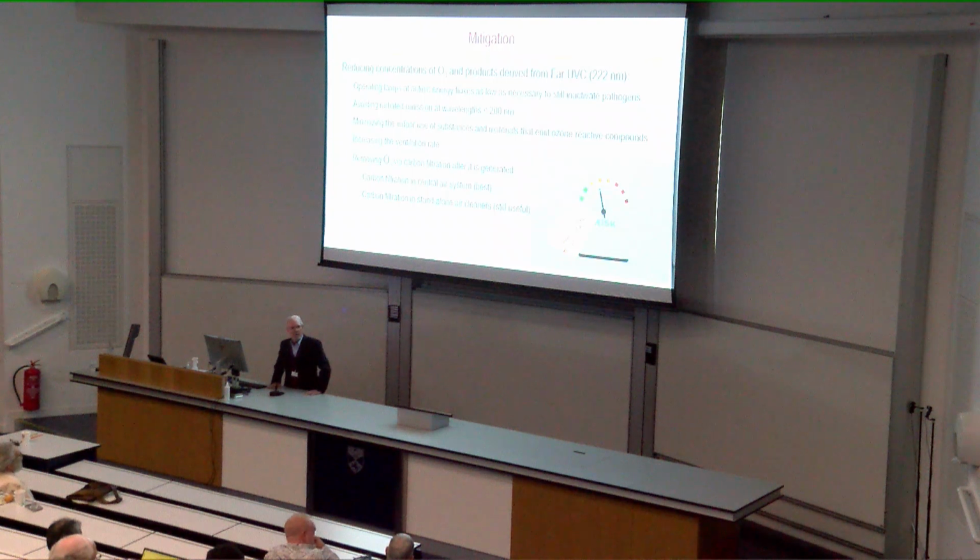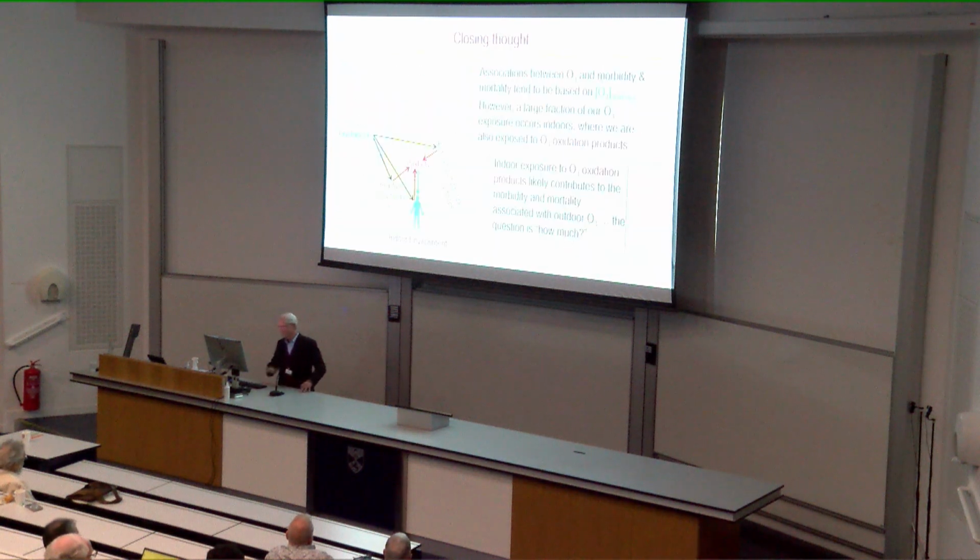If you don't have a mechanical ventilation system, if you're talking about an old classroom or a home that doesn't have central AC, standalone air cleaners can be fitted with carbon filters. You want to use enough carbon. You want to make sure that standalone air cleaner is set up, designed to remove ozone. But that can be done, and that can really reduce the chemistry. So there are mitigation approaches.